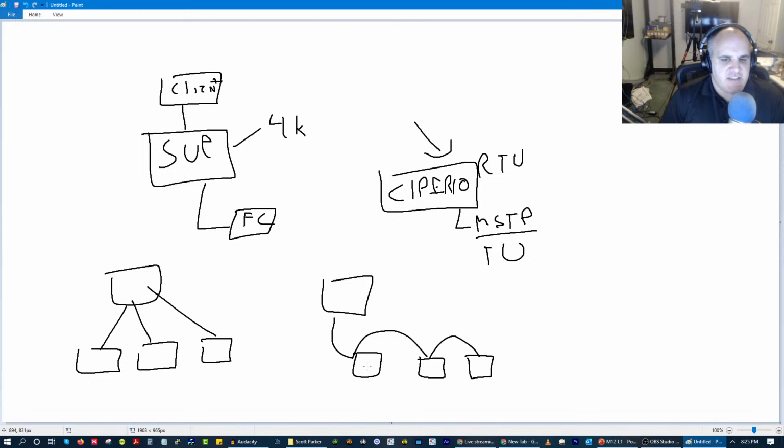What that means is that if I lose power to this IP controller right here, then I am going to lose the ability to connect to this controller as well, because electrically the signal will not continue. It's not like RS-485 where you can lose power to a controller and the signal is just going to continue on. Now, a lot of manufacturers are starting to recognize and address this, but it's still something to be cognizant of.